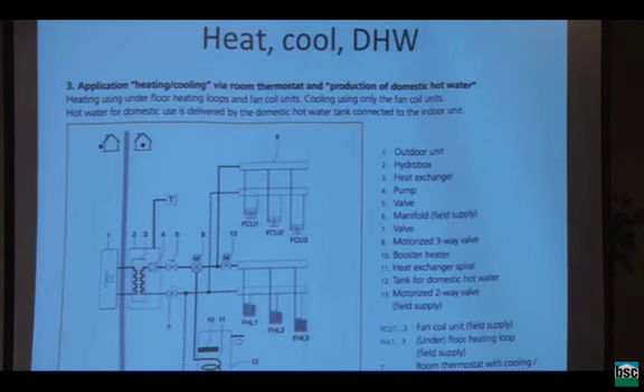Wow, that's great. Now, the one trick that they're not yet doing, but wouldn't take much, is to then say, now I could cool air with a fan coil and cause dehumidification, and take the heat and put it back into the room to get reheat. That would now be free. So I could actually make it run in dehumidification mode. They haven't yet figured out that anyone would care, but you could do that. Now, all of this can be yours for somewhere between $12,000 and $15,000, plus maybe a little bit more.